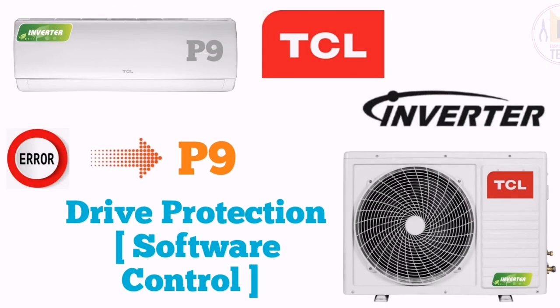When you see error P9, it means drive protection or software control. When you see this error, you have to contact the company, get the software and do the software update once in your unit. And if you do the software update and it is working, it means it was the problem of software control. And if it is not working, then you have to change the PCB and your unit will be in working condition.